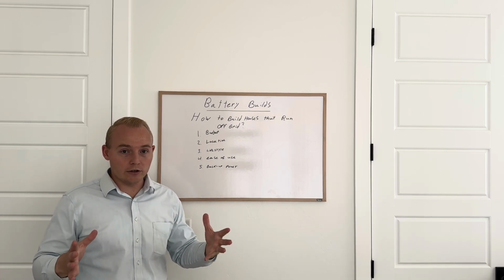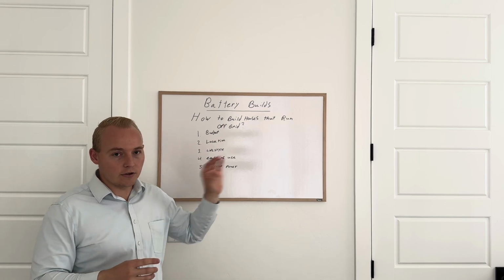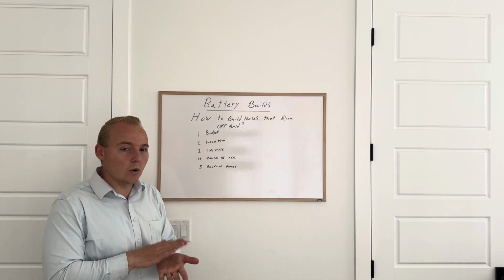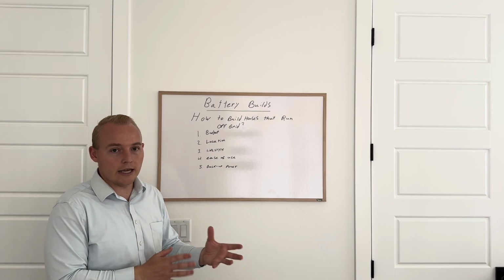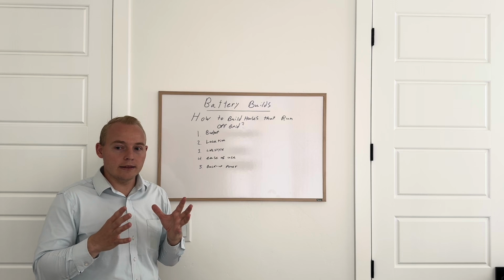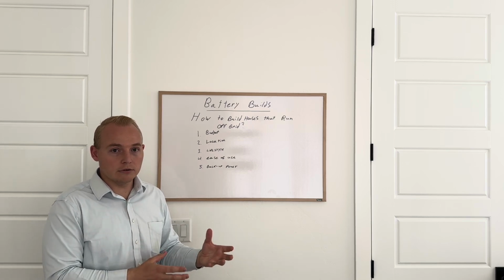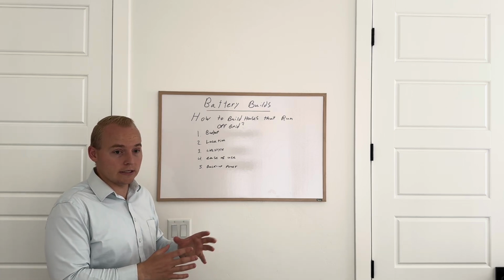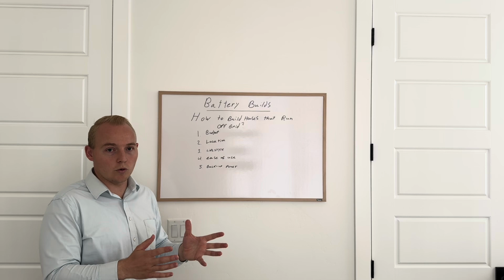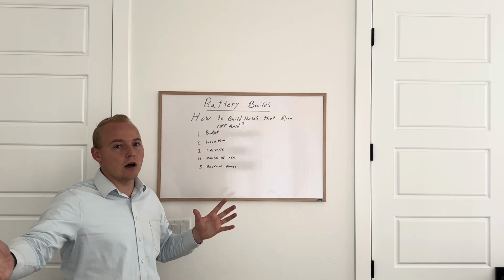And so if you have a regular HVAC system, you have ductwork, you have a heat pump outside, you have a thermostat in the house. And what we do is we control the thermostat. We have our solar system talk to the HVAC unit, and when there's a storm coming, we have it switch from electric heat mode to propane backup heat. And what that does is it takes a small solar system that can only run your house for 24 hours, 36 hours, and it makes it into a week-long backup system.